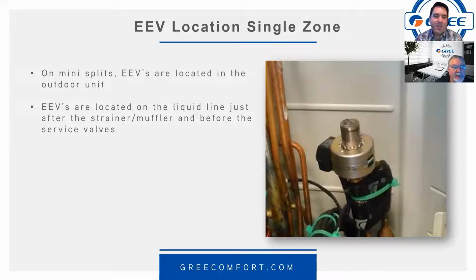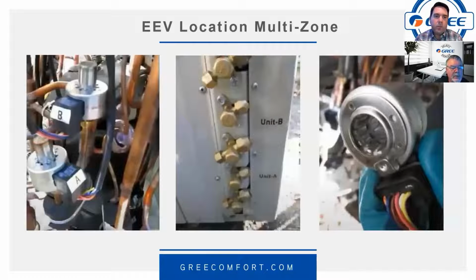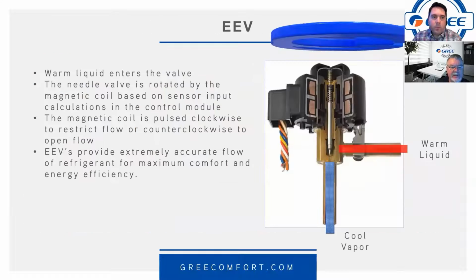So the EEV can also be a problem. On mini splits, the EEVs are located in the outdoor unit, and they're going to be on the liquid line just after the strainer/muffler and before the service valves. Multi-zone systems will have multiple EEVs in there, and as you can see, they're labeled A, B, units A and B, and the coils are easy to check and inspect and change if necessary.